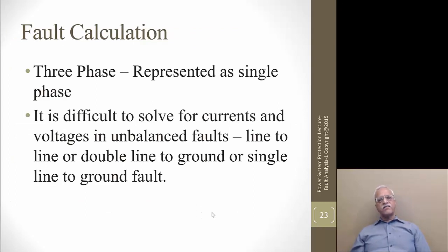Now, if I have a three-phase fault, then it is a perfectly balanced fault. It is affecting all three phases. We can still represent it as a single phase and use Thevenin's theorem or Norton's theorem or any delta-Y transformations, and we can calculate currents and voltages at different points. But if it is a phase-to-phase fault or a phase-to-ground fault, then the effect on the other phases makes it very difficult to solve for phase currents and phase voltages at different points of the network.